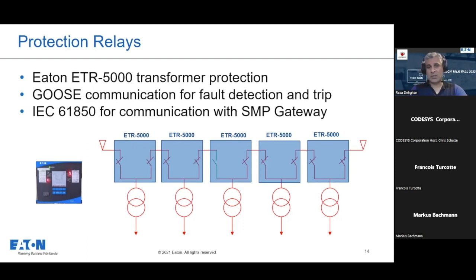The protection relay is using GOOSE communication for fault detection and trip. Basically, the protection system is on GOOSE, and then the communication between the protection system and SMP Gateway is IEC 61850, basically to exchange values and status of the relays to SMP Gateway. And with ETR 5000, the way it is designed, it can support 2 switches or 2 breakers for 1 transformer. So you can see on the diagram, let's say if you have 5 transformers, you will have 10 breakers and you will have 5 ETR 5000 relays.